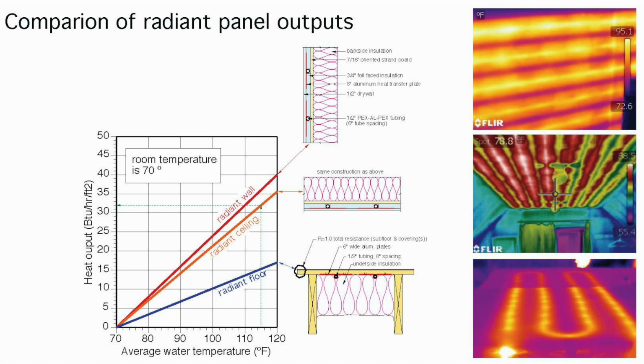Again, just some reference graphs you can look at later on. Radiant ceilings, radiant walls with plates, okay, and radiant floors. And that graph is just giving you relative performance. So you can quickly estimate how many square feet would I need on a radiant ceiling to deliver 12,000 BTUs per hour, depending on, obviously, your water temperature. Now, please, please don't do this.